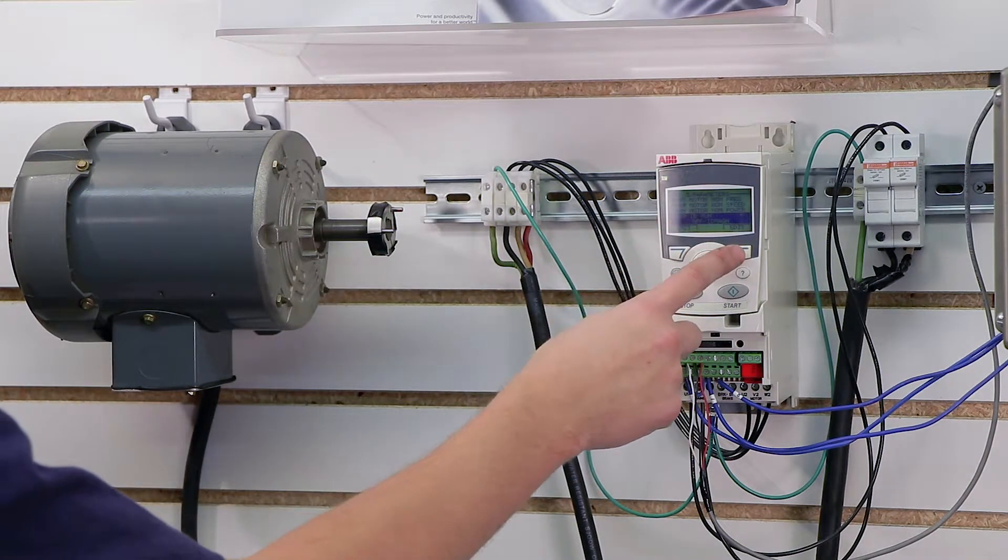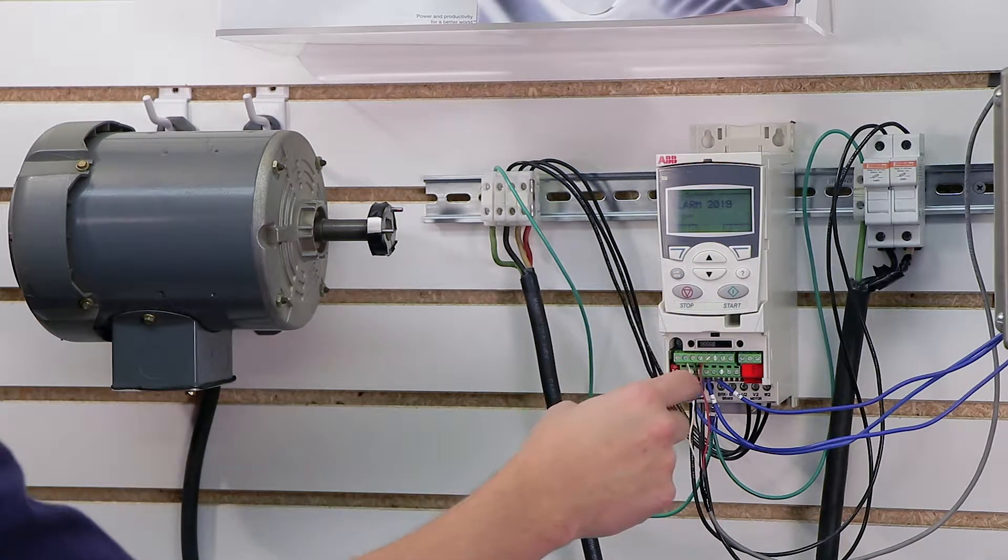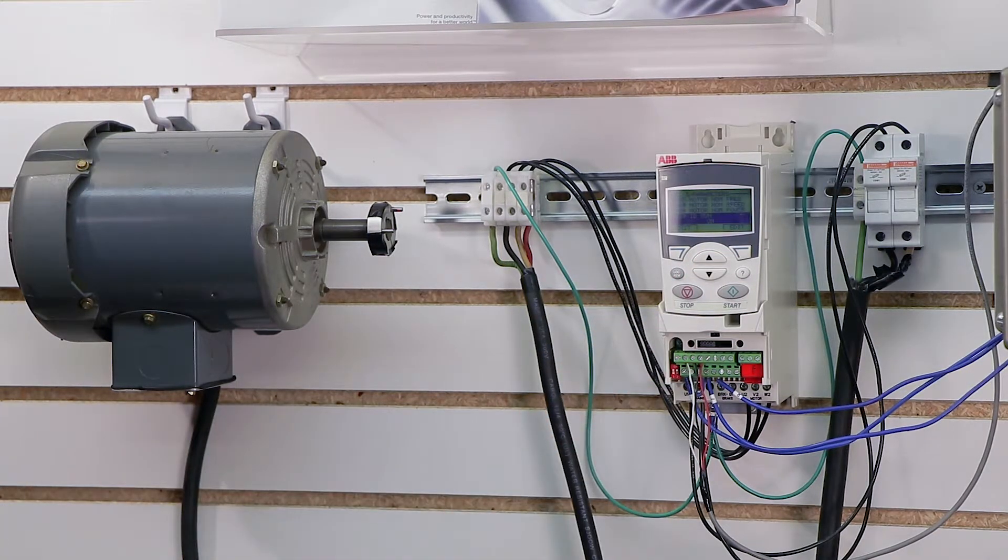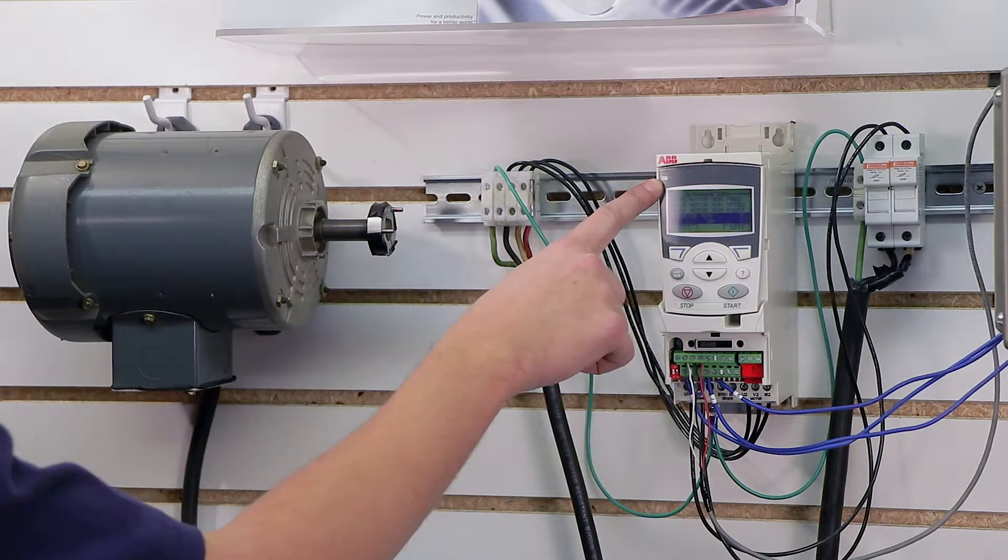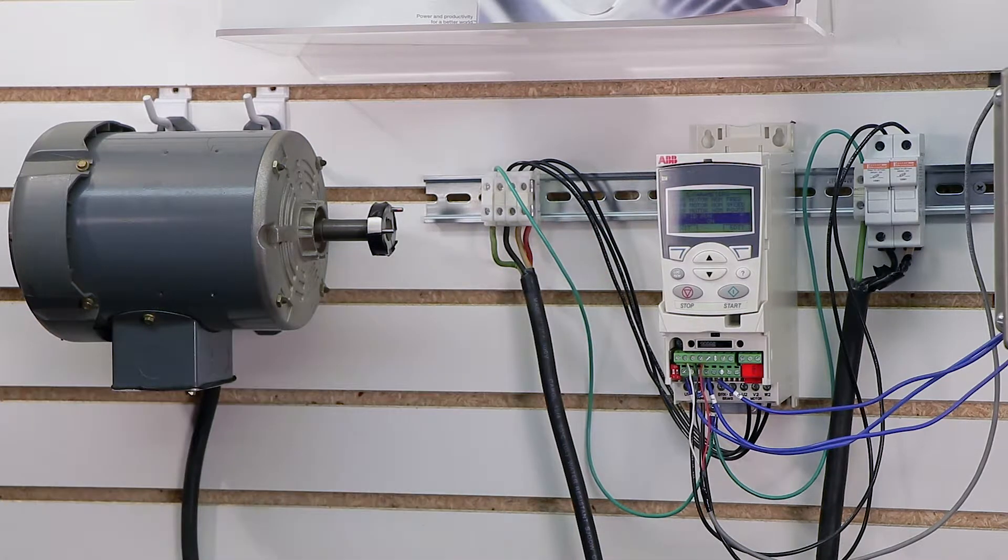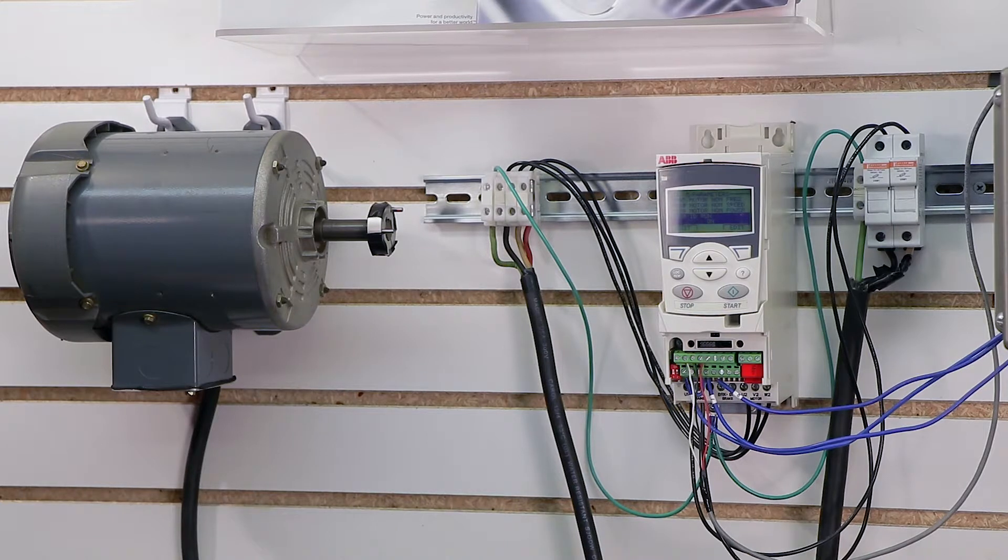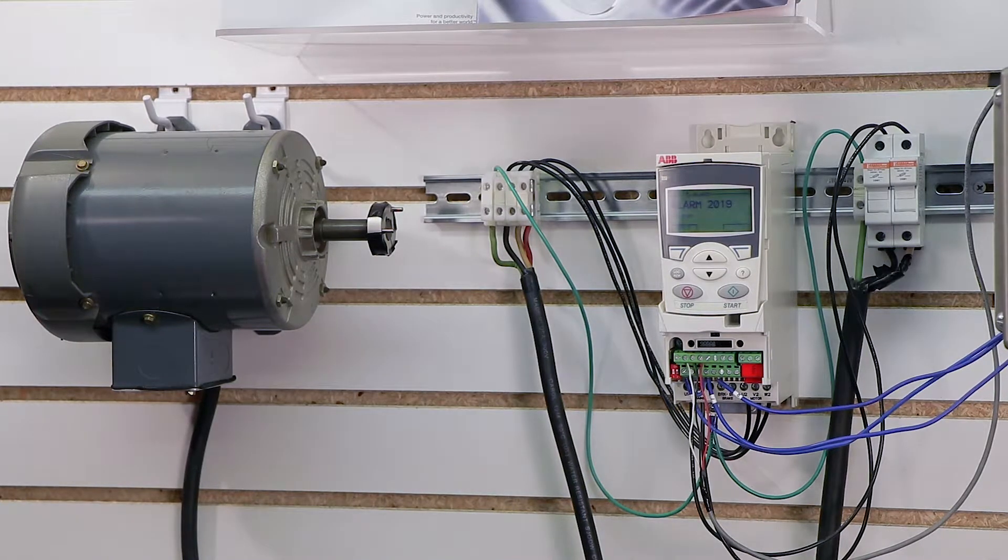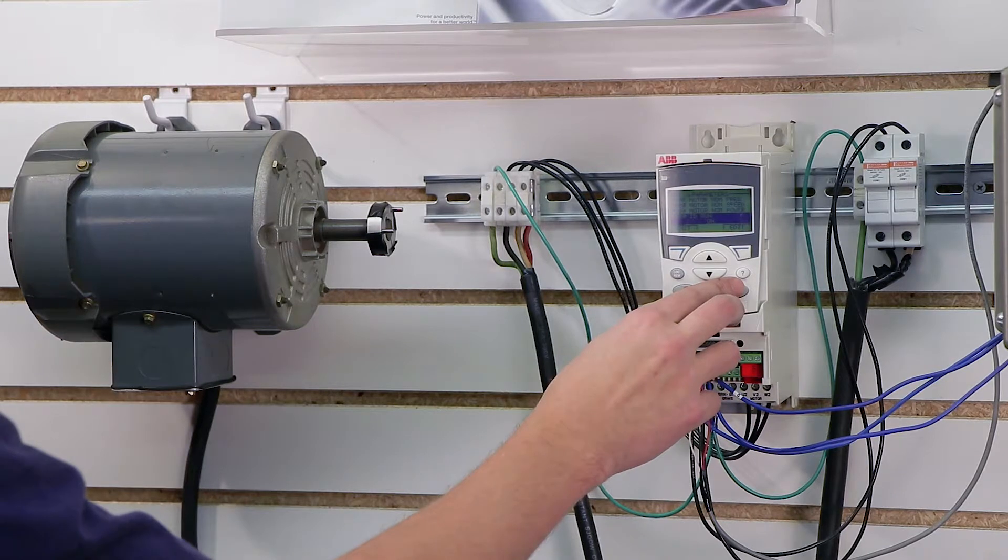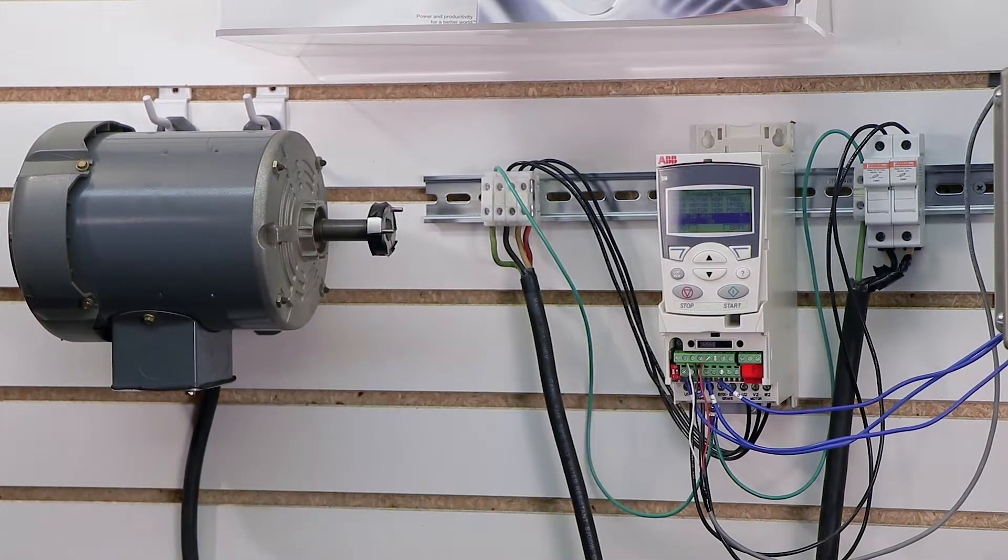And then if I go down to ID run, I can turn it on, and this will basically initialize the motor ID run or the tuning process. Notice that the light up here begins to flash, and it keeps flashing on the screen. Alarm 2019 ID run, which is essentially informing you that the motor's about to initialize the ID run on the drive. The ID run is really good because it essentially allows you to tune the drive to the motor. And so there it goes - I went ahead and pressed the start command.